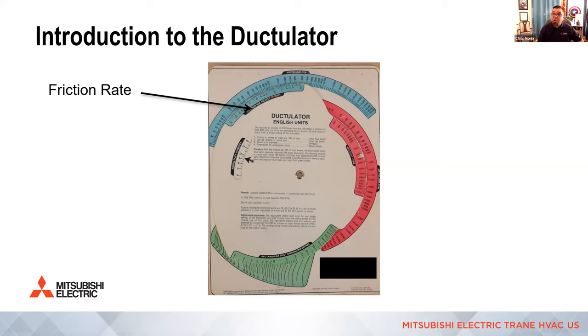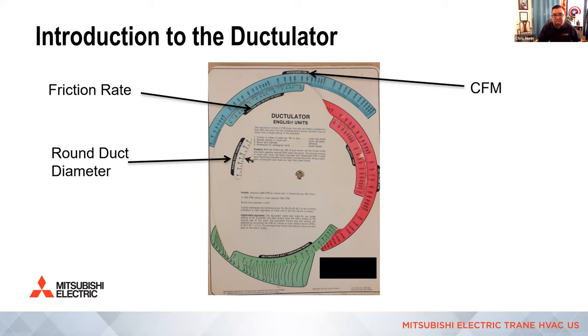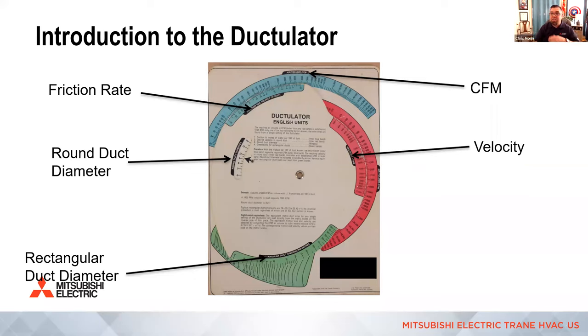So your friction rate, which we calculated in this example at 0.08, you tend to line up with the volume of air that you need, CFM. That can be in a window, or in this example, on this older style, you just line it up because it's printed on the back piece. Once you line that up, you're going to get your round size duct diameter in that first arrow. And then, of course, your rectangular duct diameter, if you're doing typically trunk duct, on the bottom in green in this example. And then the red side is velocity. We need to verify it fits within the minimum and maximum recommended, so it's actually going to mix the air in the room and it's not going to be too noisy.